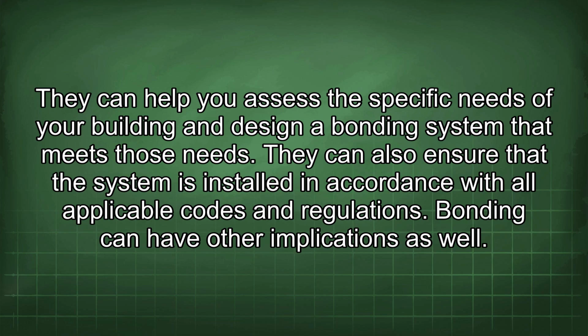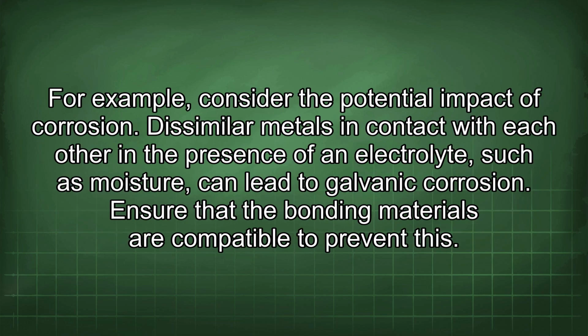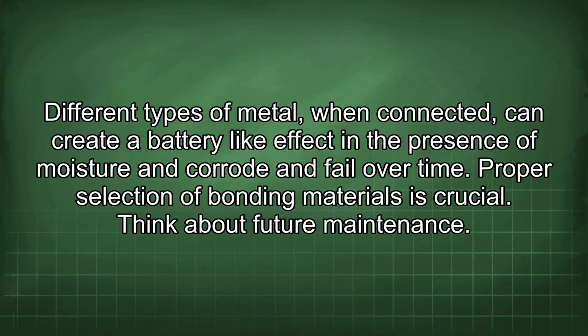Bonding can have other implications as well. For example, consider the potential impact of corrosion. Dissimilar metals in contact with each other in the presence of an electrolyte, such as moisture, can lead to galvanic corrosion. Ensure that the bonding materials are compatible to prevent this. Different types of metal, when connected, can create a battery-like effect in the presence of moisture and corrode and fail over time. Proper selection of bonding materials is crucial.